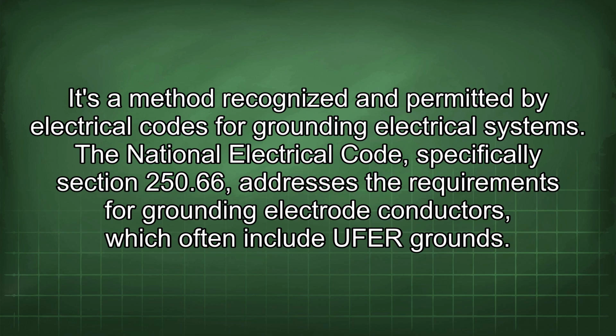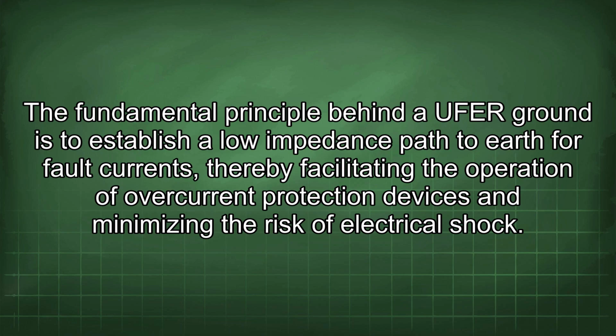The National Electrical Code, specifically Section 250.66, addresses the requirements for grounding electrode conductors, which often include UFER grounds. The fundamental principle behind the UFER ground is to establish a low-impedance path to earth for fault currents, thereby facilitating the operation of overcurrent protection devices and minimizing the risk of electrical shock.